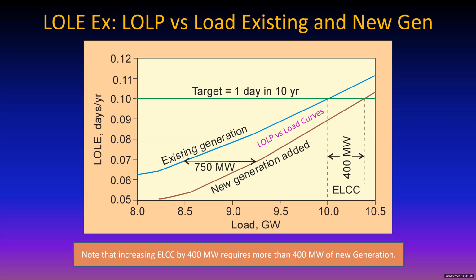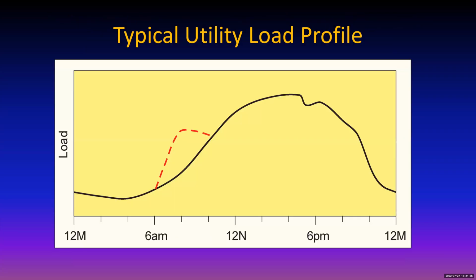We're going to look at some things. Just note that to get a 400 megawatt increase in the ELCC, you need more than 400 megawatts of new generation. Here's a typical utility load profile. The extra dotted red line is a winter peak in the morning if you've got electric heat. Otherwise, typically you peak out somewhere around 4 o'clock in the afternoon, and about 5 o'clock there's a dip, which is when everybody locks up their office and heads for home. That's when there's an increase in air pollution from automobiles, but the electric load drops down fairly quickly right about then.